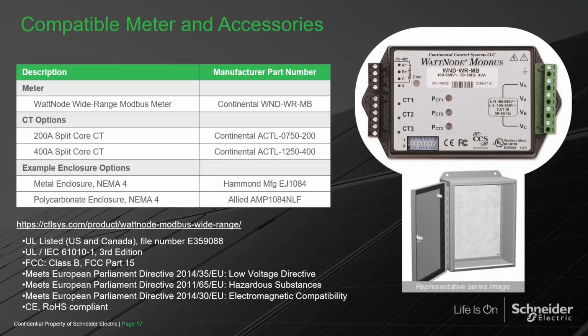This is the meter we use, basically a CT-based meter that you put at the main panel, which makes it so you don't export to the grid. This is a hard requirement in Hawaii. A lot of times people want to put their bigger loads at the main panel—they don't want to back those up with battery, but they want to offset those loads. So you put this at the main panel, and it will prevent you from exporting to the grid. Very good for self-consumption systems.